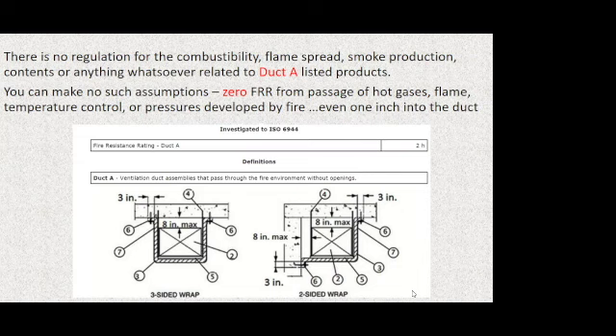And that's exactly what happens when we don't know what we're building from the very get-go. Because there's no such thing in fire duct design land where the assembly is going to be minimum SMACNA construction without locking flanges, without locking seams, without external reinforcement, except for extremely small duct sizes. And this idea that you could have this minimum SMACNA construction with one layer of something on it and somehow get to 2-hour fire resistance doesn't even pass common sense. We'll talk about that during the brief moment that we talk about grease duct.